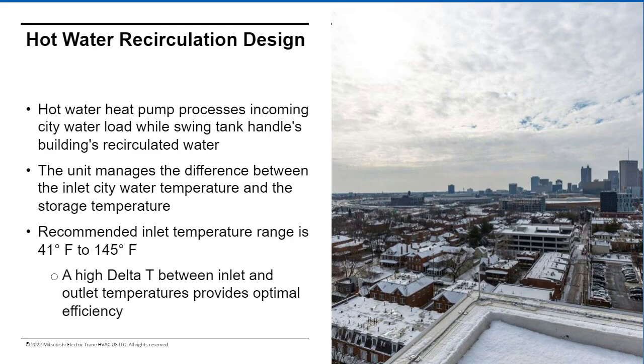As mentioned previously, the heat pump water heater processes the incoming city's cold water, while the swing tank is handling the building's recirculation water. During hot water production, the system can feed high temperature water to the swing tank, which also mixes with the warm recirculation water. Water within the swing tank is maintained within a specified temperature range, for example, 120 to 125. The swing tank typically includes a control panel with 3 electric heating elements for temperature maintenance.